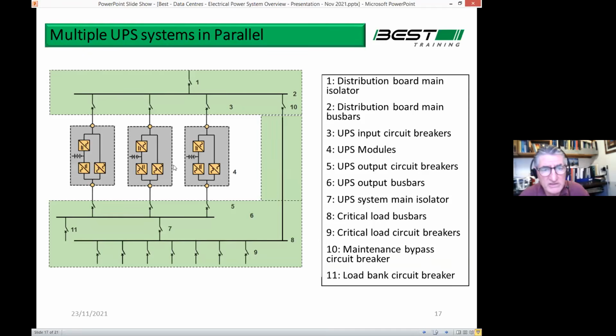And then in terms of switchgear, the switchgear for the UPS system is typically like this. This system shows 3 UPS systems, in the gray boxes. Each UPS system has a rectifier showing AC coming in one side, DC out the other. Then the battery connects into it there. And then the inverter does the opposite of the rectifier. It converts the DC back to AC and sends that onto the load. And the other little box inside the UPS there with the 2 AC lines in it represents what they call the static bypass switch. So if the system gets into trouble or it gets overloaded and the inverter can't handle the load, it transfers over onto this static bypass path and allows the power to go this way. It does a lot more than that, but that's basically its function: if there's a problem with this power path, it transfers over to here.